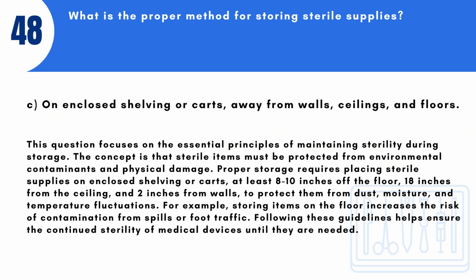The concept is that sterile items must be protected from environmental contaminants and physical damage. Proper storage requires placing sterile supplies on enclosed shelving or carts, at least 8 to 10 inches off the floor, 18 inches from the ceiling, and 2 inches from walls, to protect them from dust, moisture, and temperature fluctuations. For example, storing items on the floor increases the risk of contamination from spills or foot traffic. Following these guidelines helps ensure the continued sterility of medical devices until they are needed.